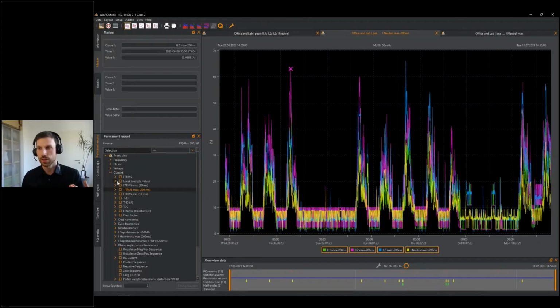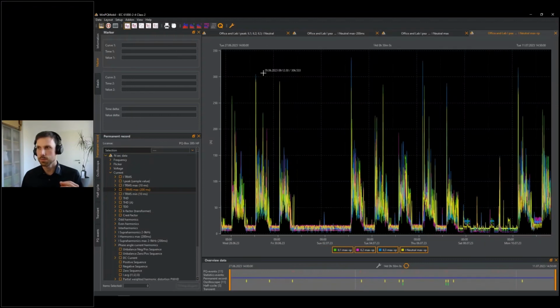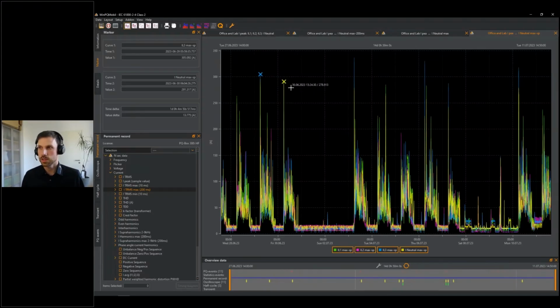And even higher values can be seen with the peak value, because the peak value goes with a sampling point. So if you go with a sinusoidal wave, you have a minimum and a maximum, and the highest sampling points are captured with the peak value. This is very interesting when, for example, you or the customer experience distortion problems with uninterruptible power supply systems. So a UPS system, if a load draws these currents, the UPS system, if it's online, has to deliver all that current, and this stresses the electronics inside. So you have to be aware of the high peak values, especially with the UPS systems.